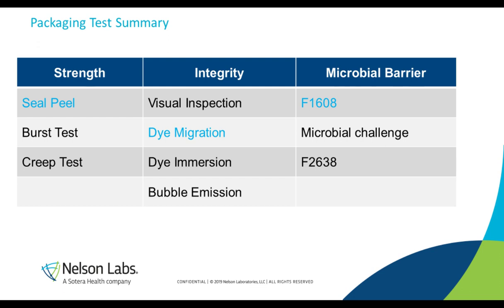Okay, so this is my packaging test summary. These are the most common test methods to meet these requirements. The strength test, you can pick seal peel, burst, and creep. Each one of these has different aspects. I'm going to go through the seal peel test. For integrity, you have 4 choices. Each one of those is different, dependent upon whether you have a rigid container, where you would use the dye immersion, or flexible, which is where most of the other test methods will come into. I'm going to show you some dye migration examples.